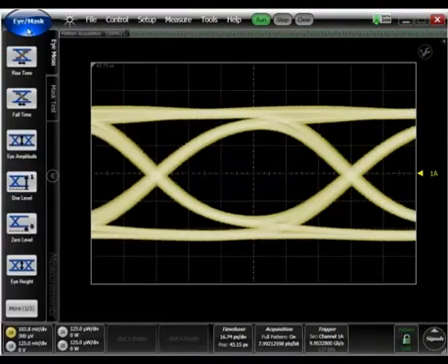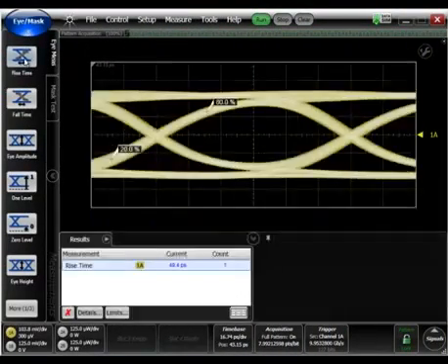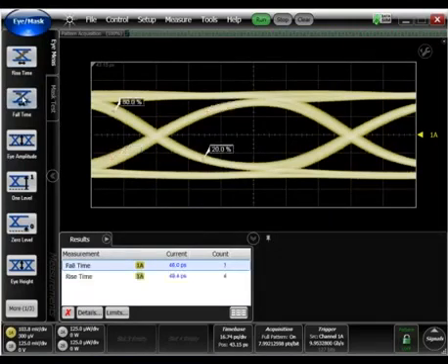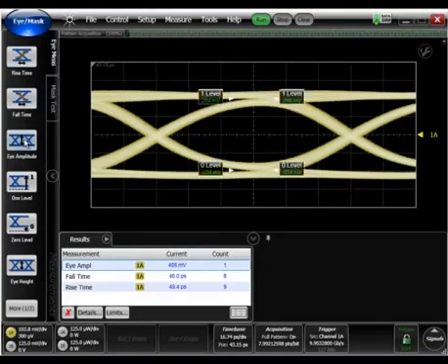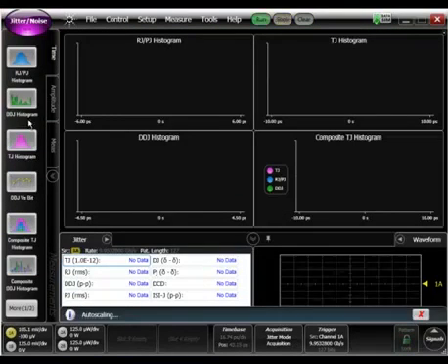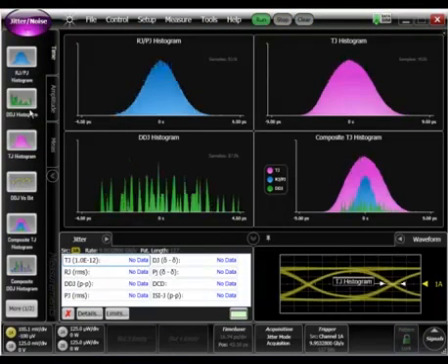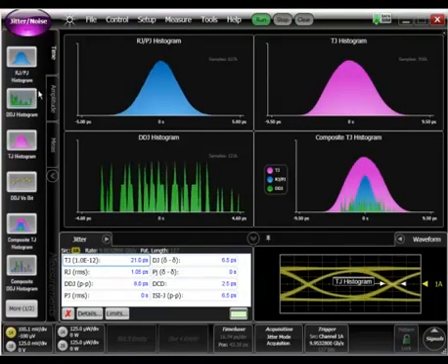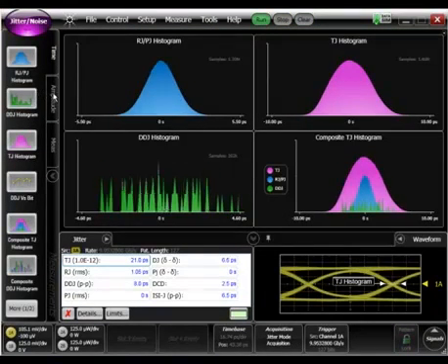Once you load the file into the FlexDCA, you can make scope measurements or eye measurements like rise time, fall time, or eye height. Switch to jitter and noise mode and make TJ, RJ, DDJ, or amplitude measurements on interference and noise.